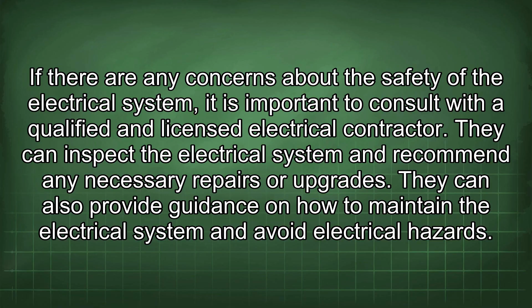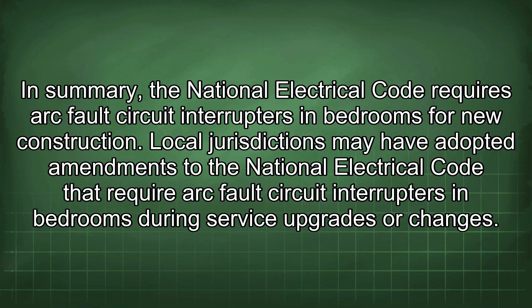In summary, the National Electrical Code requires arc fault circuit interrupters in bedrooms for new construction. Local jurisdictions may have adopted amendments requiring arc fault circuit interrupters in bedrooms during service upgrades or changes. Consult with the local authority having jurisdiction to determine the specific requirements in your area.